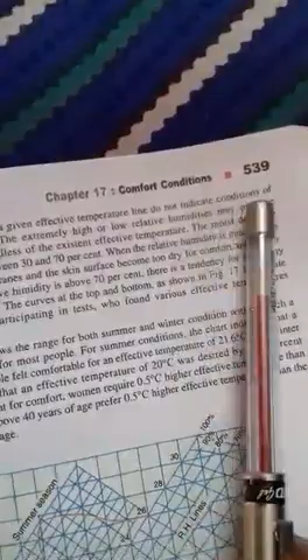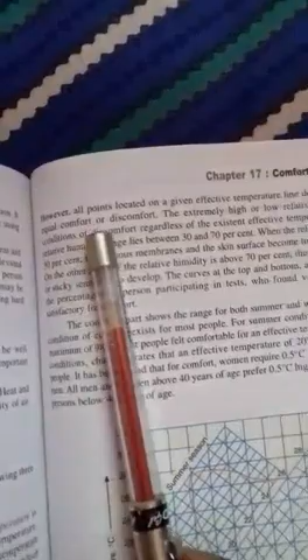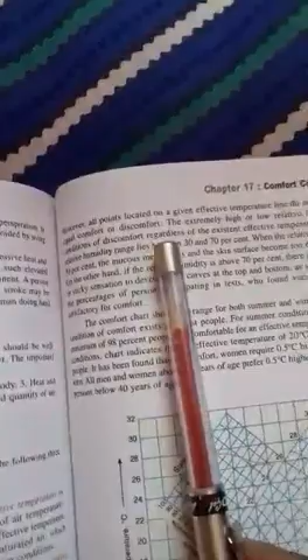The statistically prepared graphs corresponding to summer and winter season are also superimposed. These graphs have effective temperature scale as abscissa and percentage of people feeling comfortable as ordinate. A close study of the chart reveals that several combinations of wet and dry bulb temperature with different relative humidity will produce the same effective temperature. However, all the points located on the given effective temperature line do not indicate equal comfort or discomfort. Extremely high or low relative humidities may produce conditions of discomfort regardless of the effective temperature.